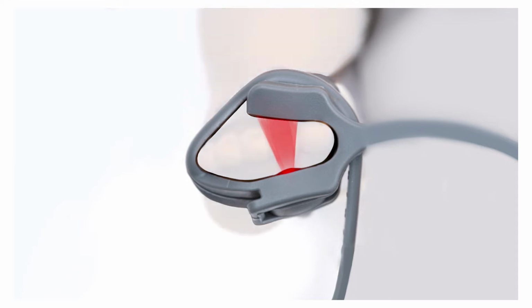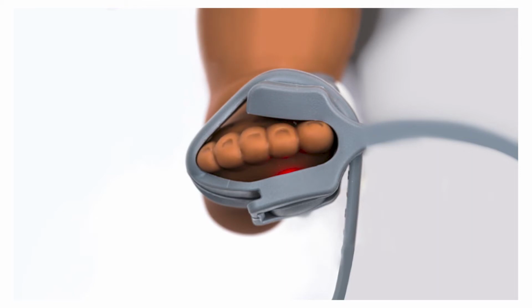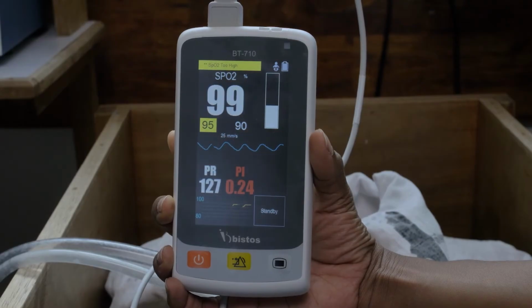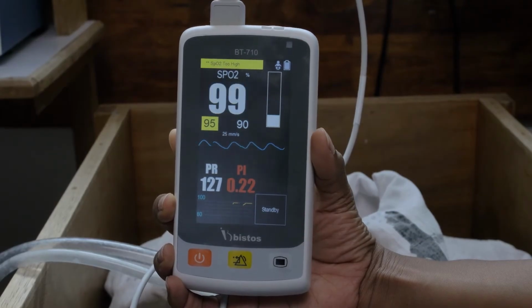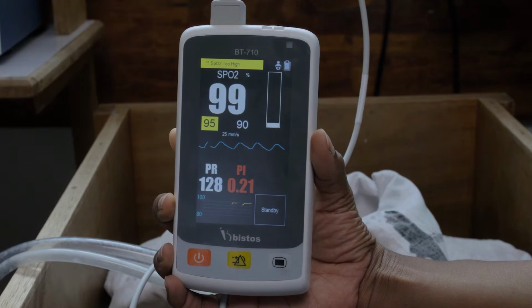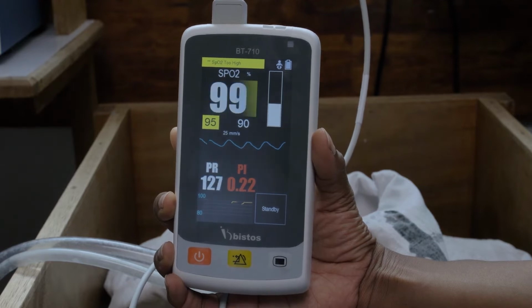As the light passes through the arterial red blood cells which carry oxygen to the baby's foot, it is absorbed in different amounts, depending on whether the cells are saturated with oxygen. With this information, the microprocessor in the pulse oximeter is able to work out the oxygen saturation, or SpO2. For most sick children, this is a key indicator. If their saturation is low, it means they are not getting enough oxygen to supply the needs of their body.